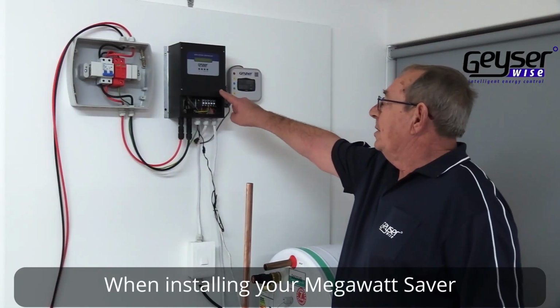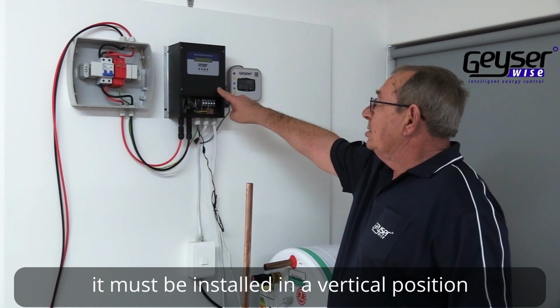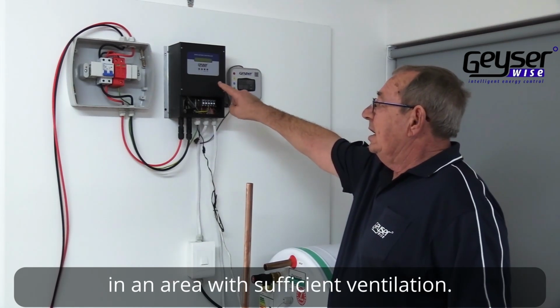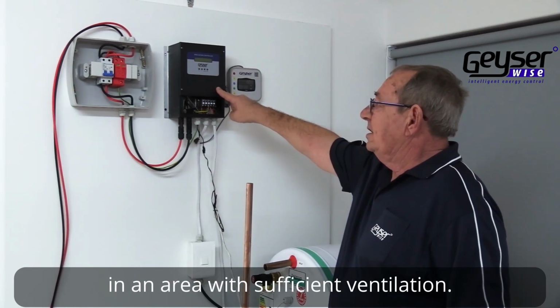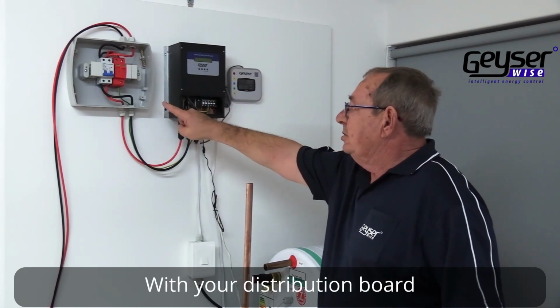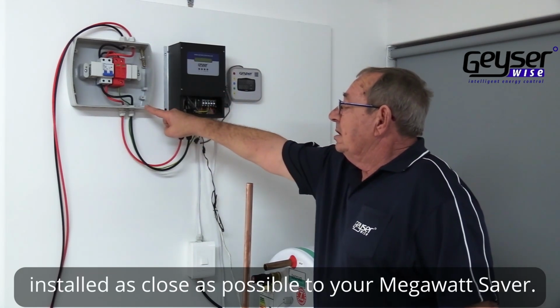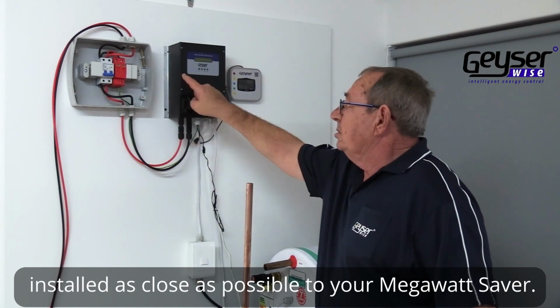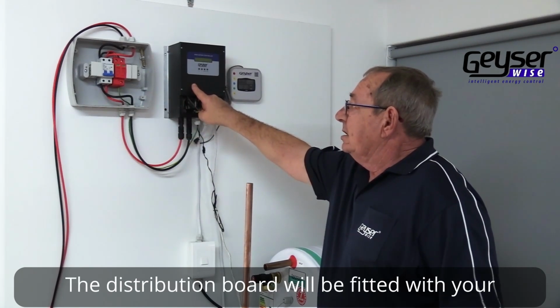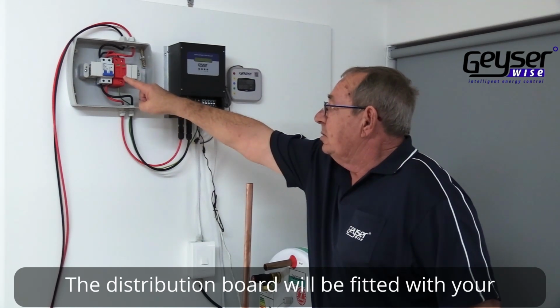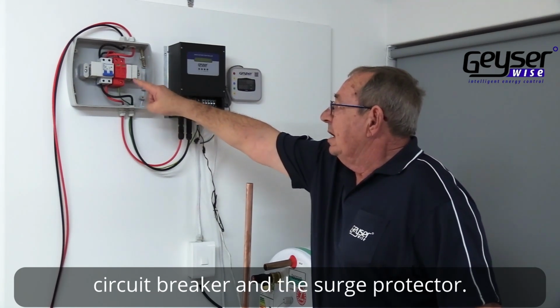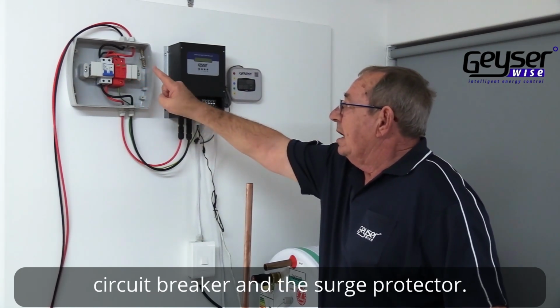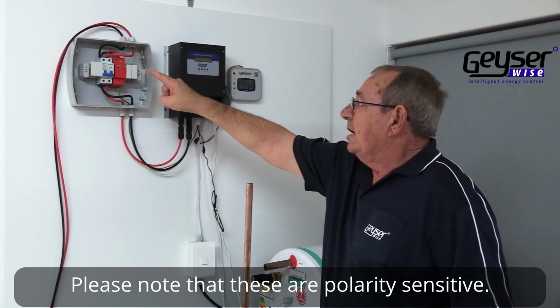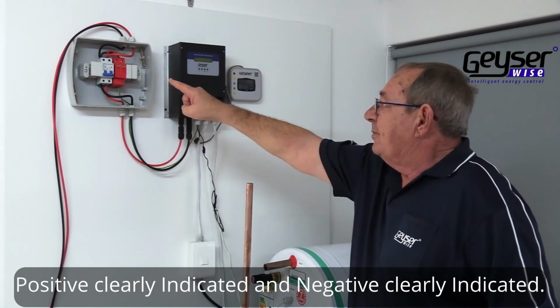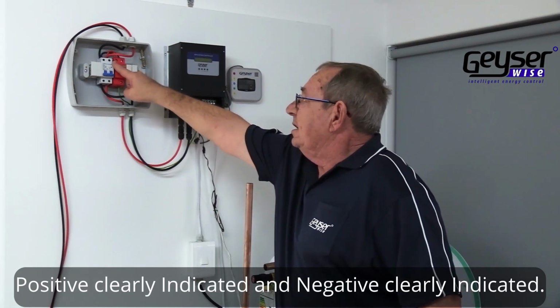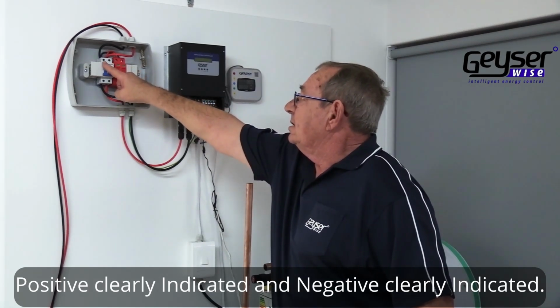When installing the Megawatt Saver, it must be installed in a vertical position in an area with sufficient ventilation. The distribution board should be installed as close as possible to the Megawatt Saver. The distribution board should be fitted with the surge protector and DC circuit breaker. Please note that these are polarity sensitive. Positive and negative are clearly indicated on the circuit breaker as well as the surge protector.